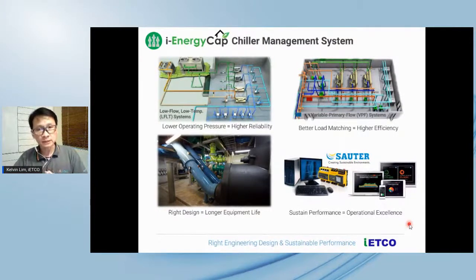Let's talk about, like Engineer Chen mentioned, the right engineering design. You can implement low flow design, low temperature design, variable primary flow, pumping the right flow based on demand, getting the design right so you get longevity in the equipment. But again, you need a building management or chiller management system, and monitoring, to sustain performance in a building.